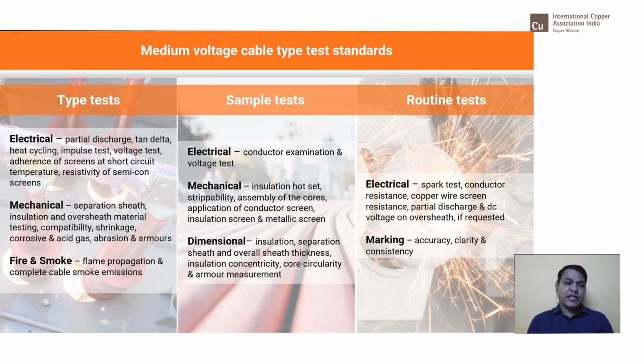Corrosive gas and acid gas for the low smoke zero halogen sheath cables and armors are tested as well. Fire and smoke when it comes to PVC or low smoke zero halogen cable. So sample tests are basically where the contractor or third party witnesses conductor examination, and some insulation hot set test, which is applicable for XLPE insulation, strippability of screen and dimensional checks. So routine test, as you can see, in the medium voltage, high voltage, the partial discharge has to be done as a routine test.